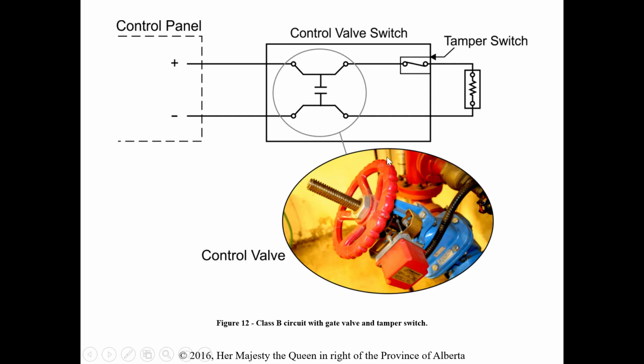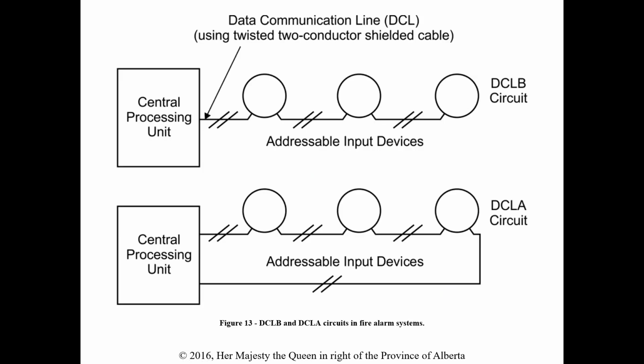Again, same scenario. If it's got a switch attached to the position of the control valve where it needs to be in the open position, if somebody walks up and tries to close it, there's going to be a supervisory alarm on that, and it's going to go back to the panel and let you know that that is not operational any longer.